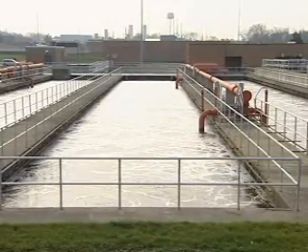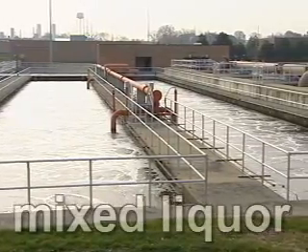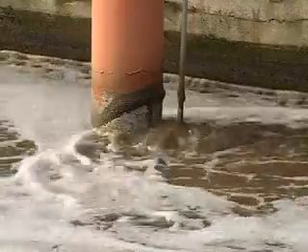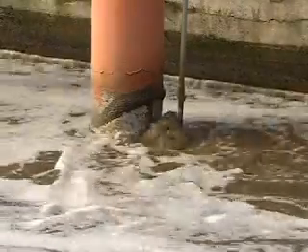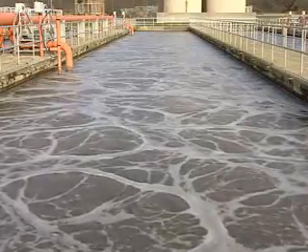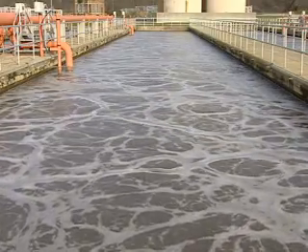The flow from the primary tank enters the secondary treatment tank and is mixed with sludge from the clarifier to form a mixed liquor that is treated in an aeration tank. Air and microorganisms are added to the mixed liquor to break down the organic pollutants. The aerobic organisms thrive in this nutrient-rich environment; they consume and subsequently remove the vast quantity of organic matter dissolved in the water. The microorganisms gather on the organic matter to form floc.